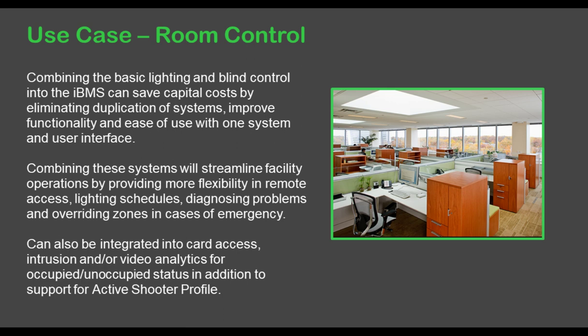A lot of times I was working on a hospital up north, and the shade and blind control is in like division 8 and 12. So when you think about it, it's completely siloed from the BMS, or division 25 for that matter, 23, 25. So what we found out was they were putting in a whole separate system to do that. And you just start having conversations about, couldn't we combine that into the same control system that's already in the building? I've already got to have something in there for controls.